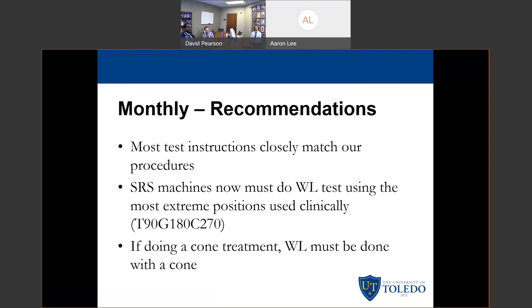Looking more thoroughly at the monthly recommendations, most of the ways they describe performing tests actually match existing procedures quite well. Some things they mentioned: SRS machines must now do Winston-Lutz — before, Winston-Lutz was never even explicitly stated in TG-142. They say you must do Winston-Lutz and must use the most extreme positions used clinically. If your machine is going to do a T90, G180, or C270 beam, you should probably include that in your Winston-Lutz, and beyond that they say to use professional discretion on what angles and positions to use for your machine.